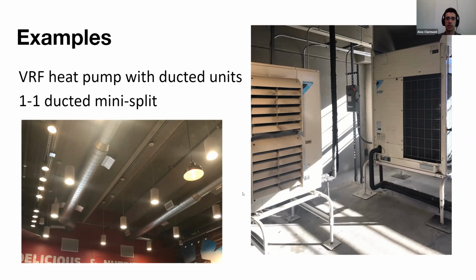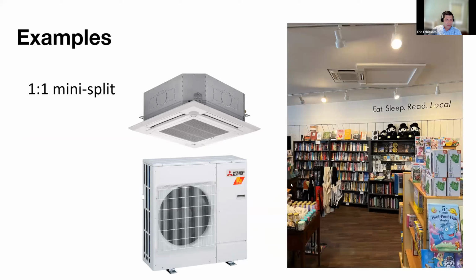Eric, I believe you had some examples as well you wanted to share. Yep. Just want to go to the next slide. All right, so this was an example of a one-to-one mini split in a bookstore. They just needed a little more cooling for their retail area, so they installed a 4-way cassette so they can get all corners of the retail area. You can see the access panel there on the right is rather large. So again, always talk to your engineer or your installing contractor. There might be some local building codes that require access panels larger than recommended by the manufacturer.